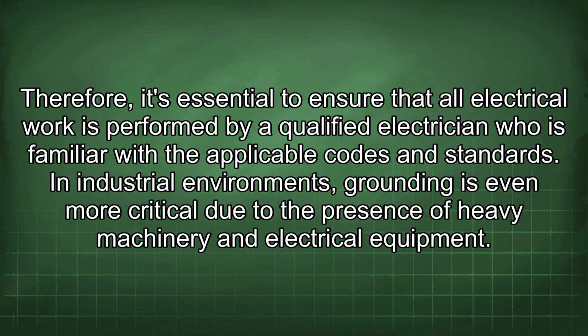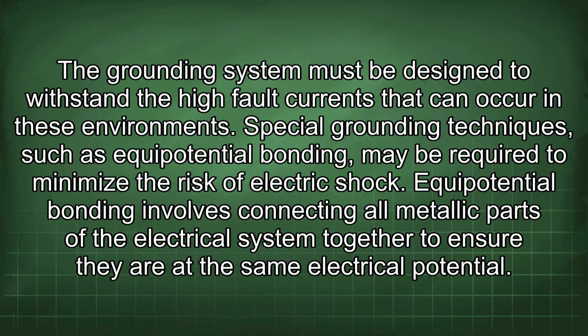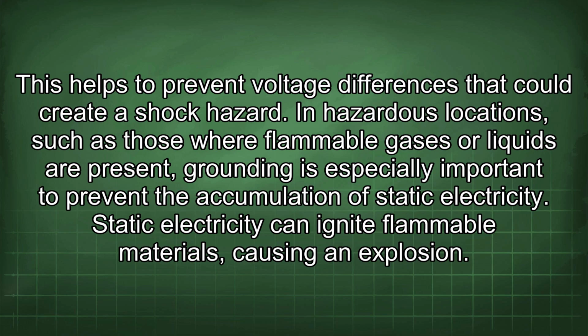In industrial environments, grounding is even more critical due to the presence of heavy machinery and electrical equipment. The grounding system must be designed to withstand the high fault currents that can occur in these environments. Special grounding techniques, such as equipotential bonding, may be required to minimize the risk of electric shock. Equipotential bonding involves connecting all metallic parts of the electrical system together to ensure they are at the same electrical potential. This helps to prevent voltage differences that could create a shock hazard.